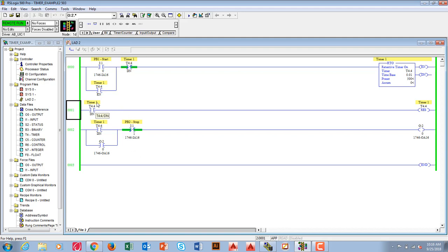Well, this is getting done. Okay, so it's running its logic inputs here, causing the output, the timer, to run, and then the timer gets done, so it runs its inputs again. We've no longer made this. You know, we've got a holding circuit. This gets done and this gets done, and then what it does is it will go ahead and write the outputs. Well, when it writes this output for the reset, this is then no longer done. So by moving the reset around in your program, you can get things to occur in different ways.